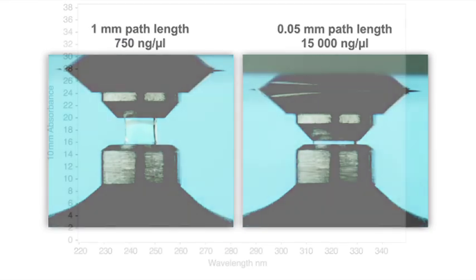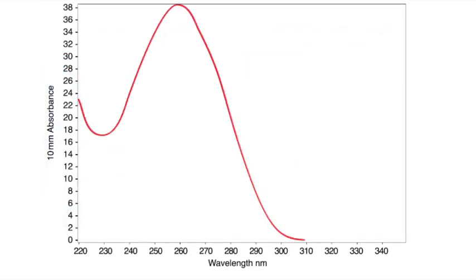The vertical path length can automatically change in real time during the measurement. Shortening the path length enables the measurement of higher concentrations, effectively removing the need to perform dilutions for most nucleic acid samples.